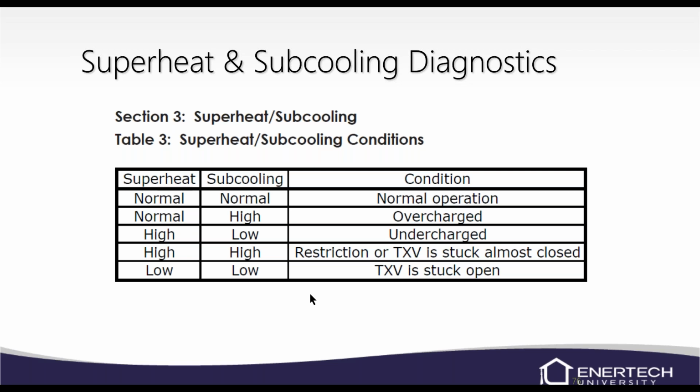Unless something happens to that spring on the bottom of that valve. I've never seen anything happen to those springs. That spring will always slam that valve shut. So that's why it's either going to be restricted halfway or it's going to be stuck closed, more than likely.